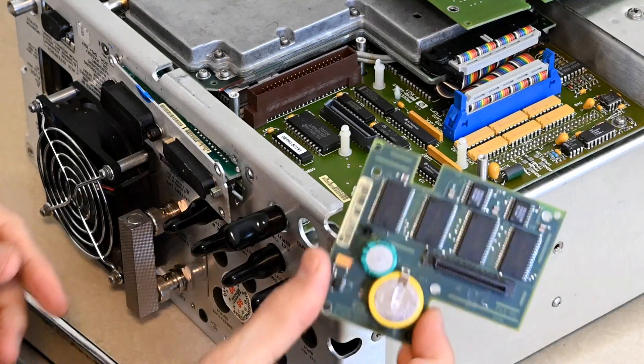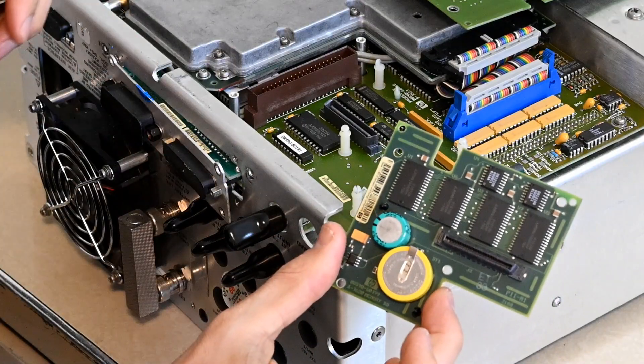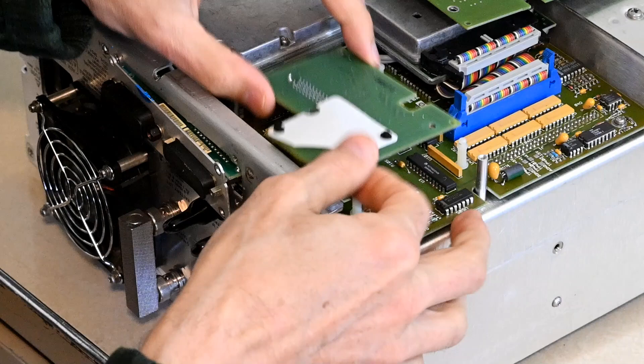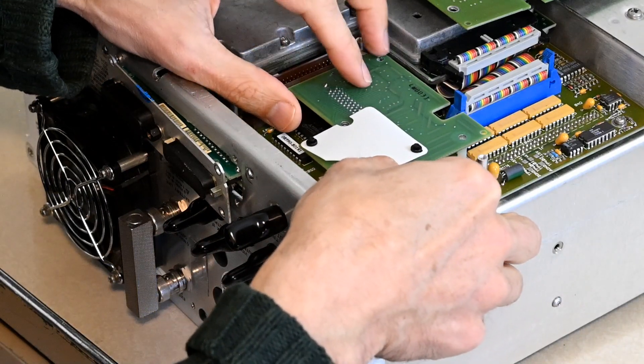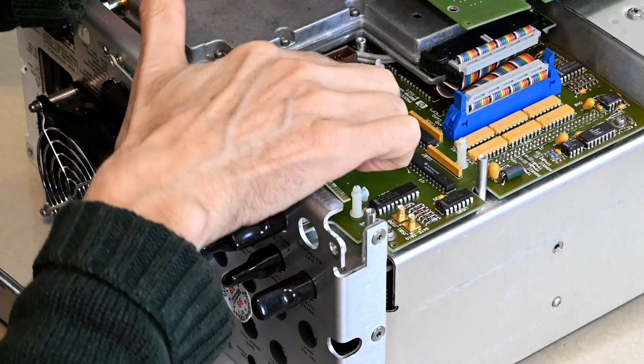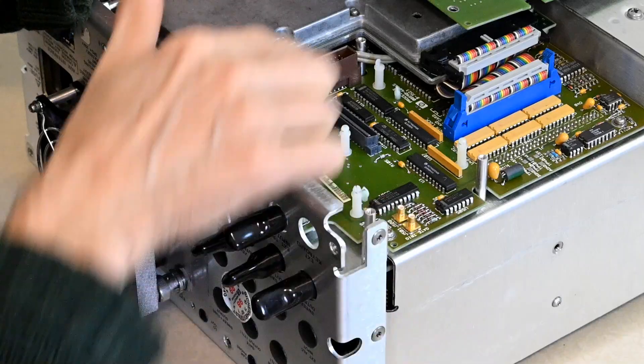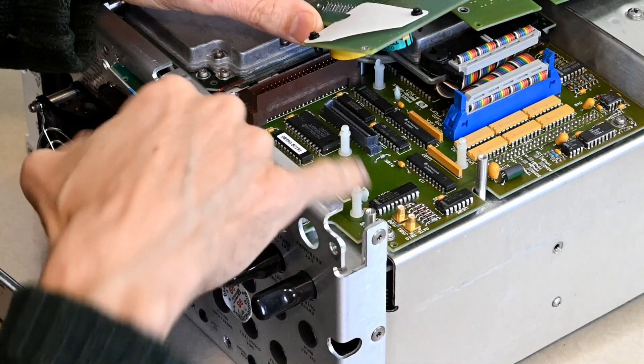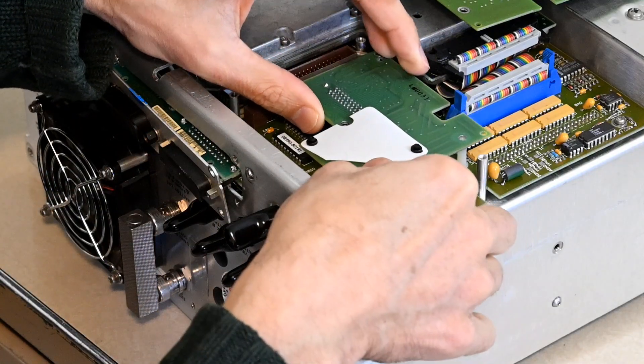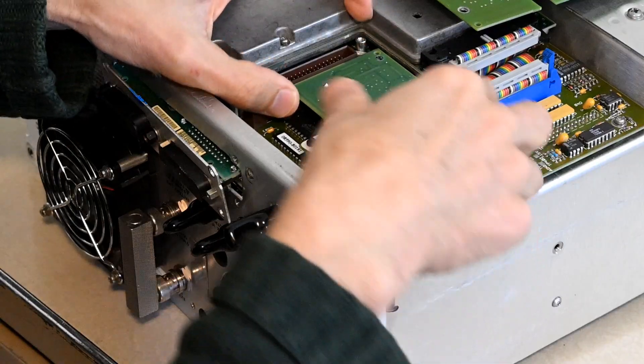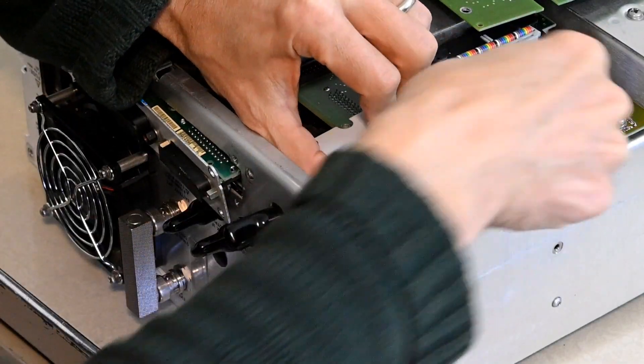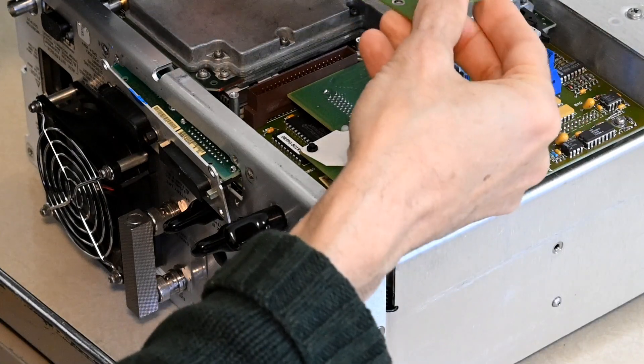Here is the instrument. Here is the board that we just got the battery replaced on. This one is going to snap in right there. There's these four clips; this one back here is broken. It was broken when I got it off, presumably the last person had a hard time taking it apart. These are just clips, so the only thing we have to do is align them and clip it together. That is snapped into place.